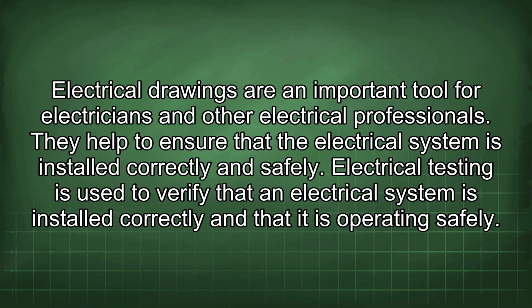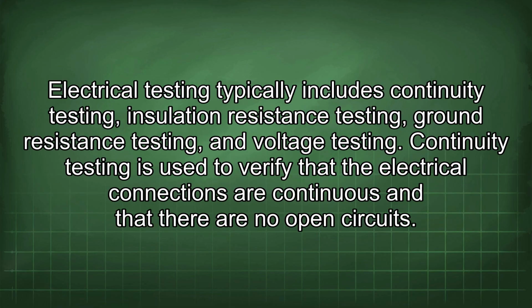Electrical drawings are an important tool for electricians and other electrical professionals. They help to ensure that the electrical system is installed correctly and safely. Electrical testing is used to verify that an electrical system is installed correctly and that it is operating safely. Electrical testing typically includes continuity testing, insulation resistance testing, ground resistance testing, and voltage testing. Continuity testing is used to verify that the electrical connections are continuous and that there are no open circuits.